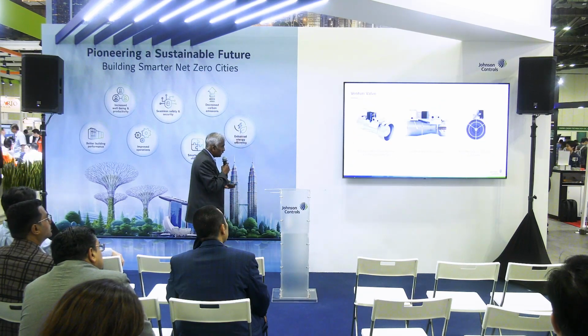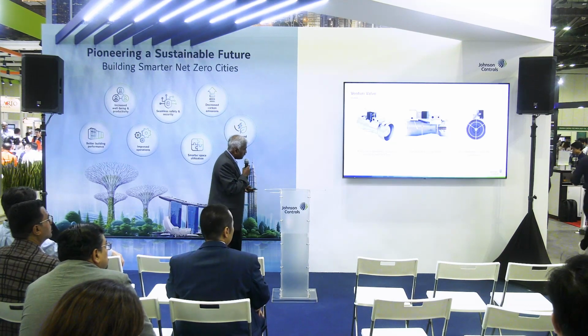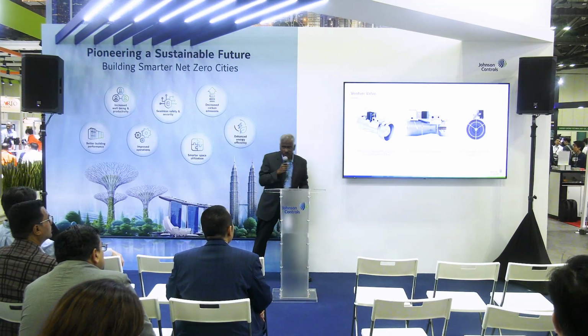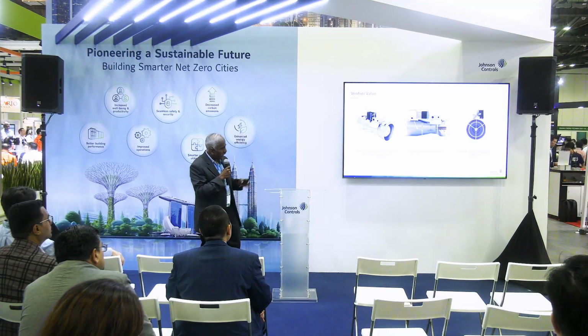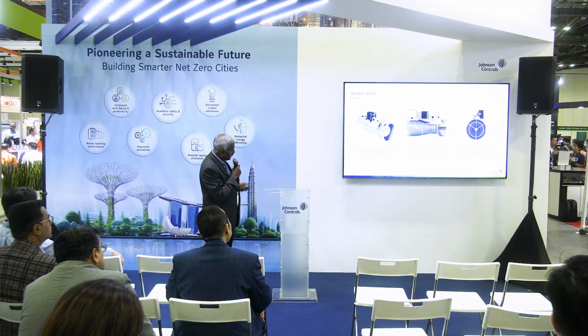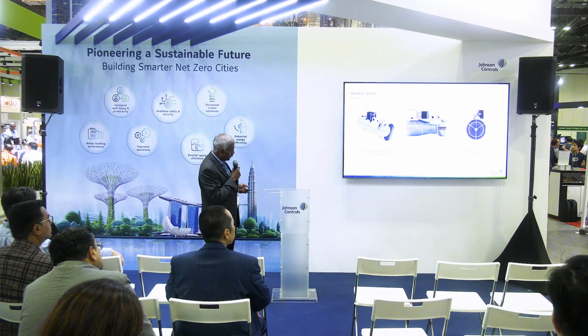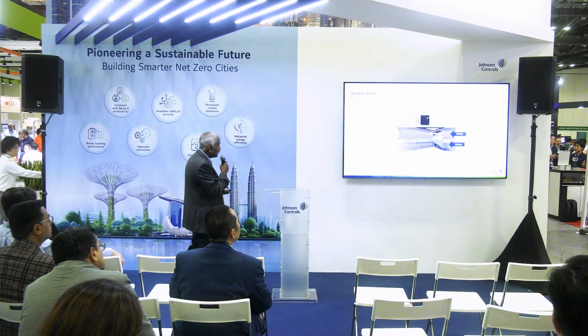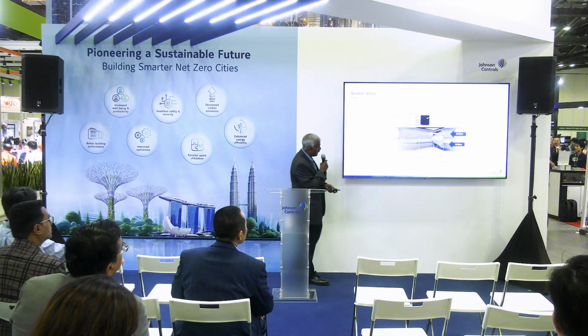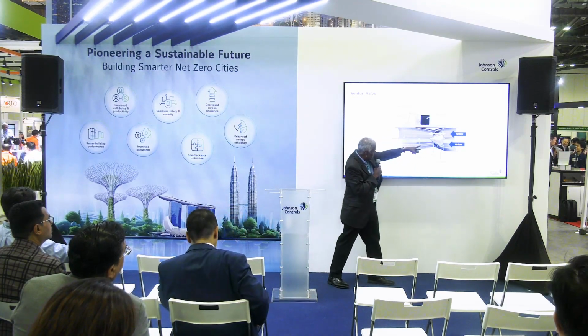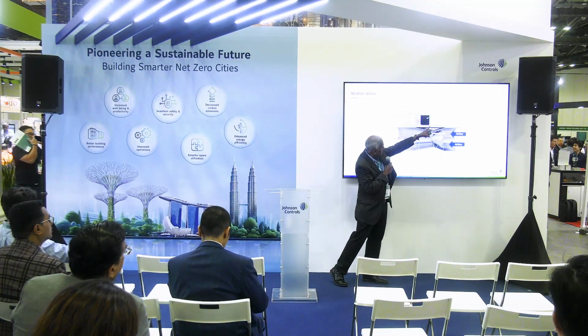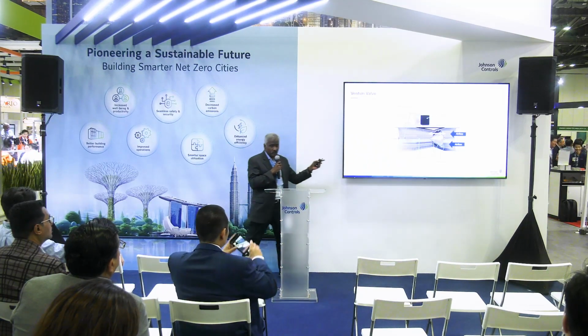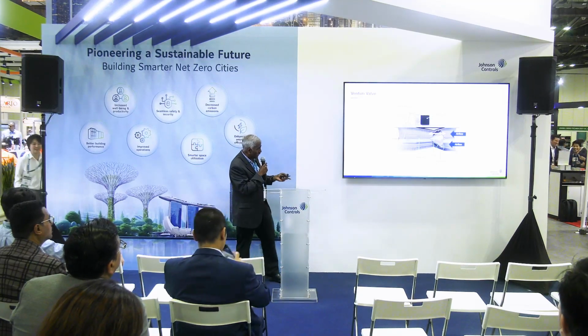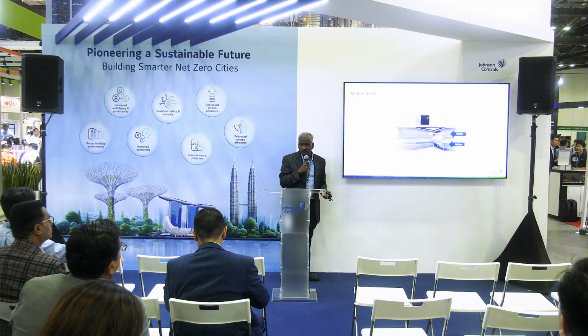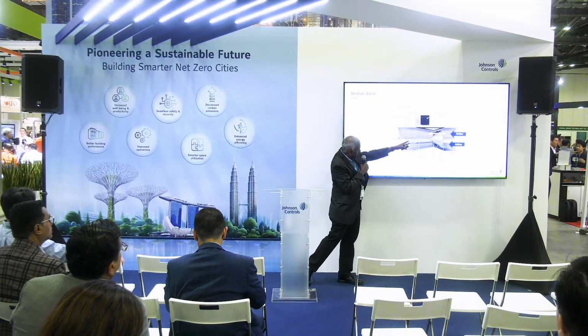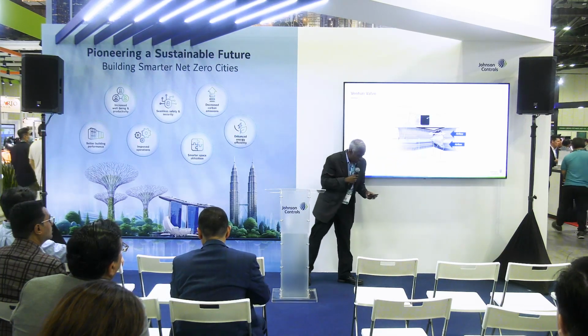So let's talk about the Venturi valve. This is typically the design of the Venturi valve. It's usually pressure independent, and it's totally different from a VAV box. If you see a VAV box, you have a blade that opens and closes. But this is a conical solution. If you look at the design, it has an actuator, it has a shaft, and it has a cone. So this is fundamentally how a Venturi valve looks, right? As I mentioned earlier, we have the actuator, the shaft, and the cone that moves up and down. The actuator is controlled by the controllers, be it the CCM or the standalone controllers. That triggers, let's say you want 100 CFM or 1000 CFM, and the controller moves it. The cone moves and the airflow comes in.